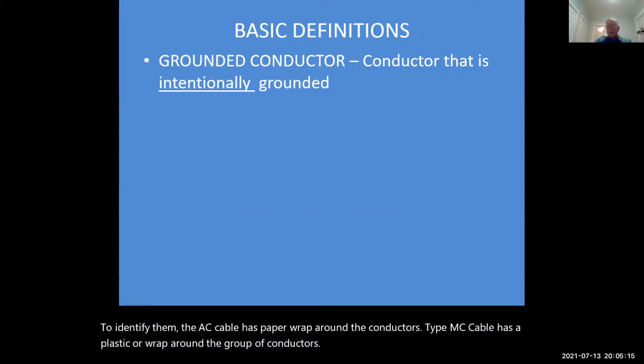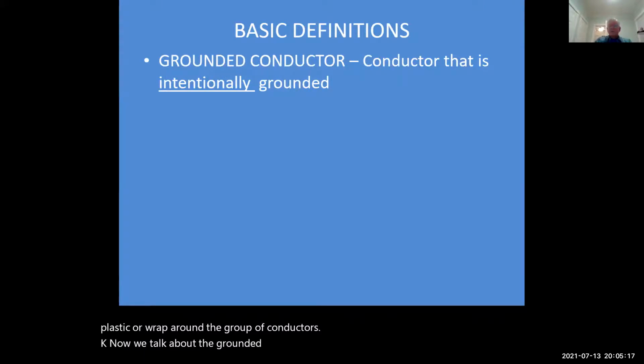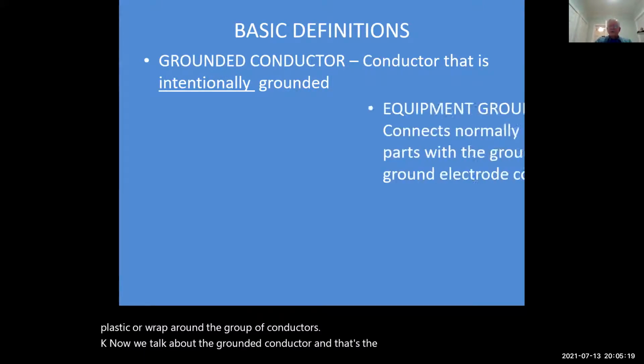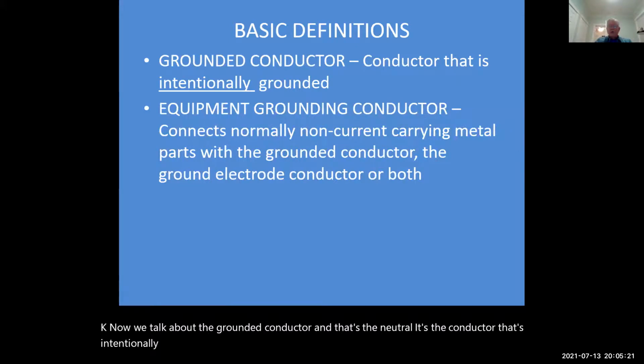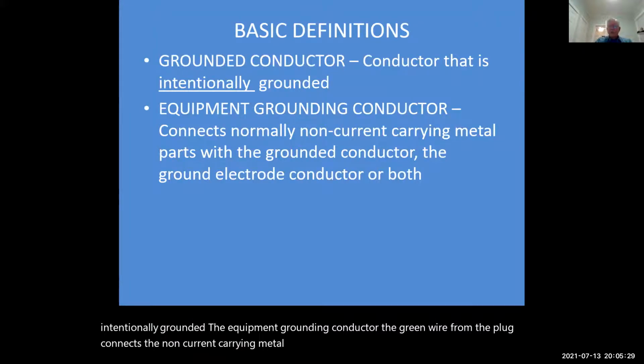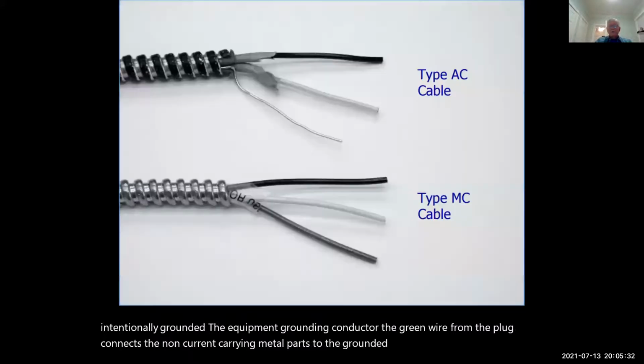Okay, now we talk about the grounded conductor, and that's the neutral. It's the conductor that's intentionally grounded. The equipment grounding conductor, the green wire in the plug, connects the non-current carrying metal parts to the grounded conductor, the ground electrode, or both.